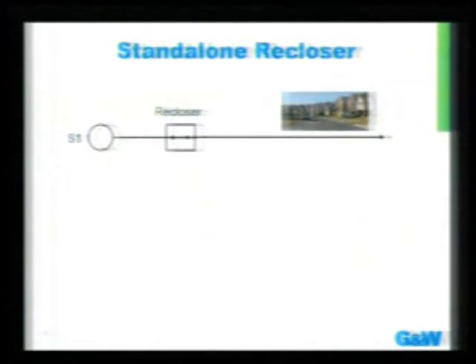So if there is an issue, say a tree falls on one of the lines, or there's some kind of wildlife on the line, there will first be a fault. The recloser will detect this and open to isolate the problem, and then, as its name implies, it will reclose to attempt to feed power again. If the problem still exists, it opens once again.